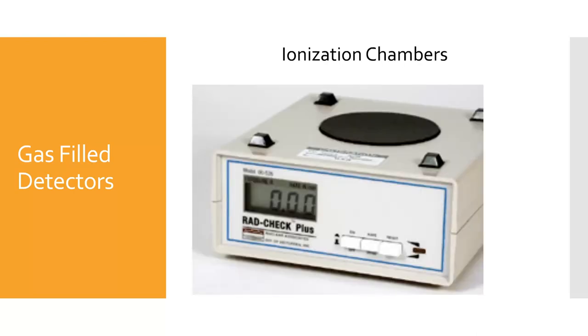Now that we are aware of how gas-filled detectors work, let's look at some examples. The first is an ionization chamber. These devices are highly accurate. The chamber of gas is inside the device, and as the radiation interacts with the gas atoms, the number of freed electrons is proportional to the radiation causing the ionizations. Ionization chamber devices are often used to test the output of X-ray tubes, as well as detect radiation in fluoroscopic systems and nuclear medicine generators.